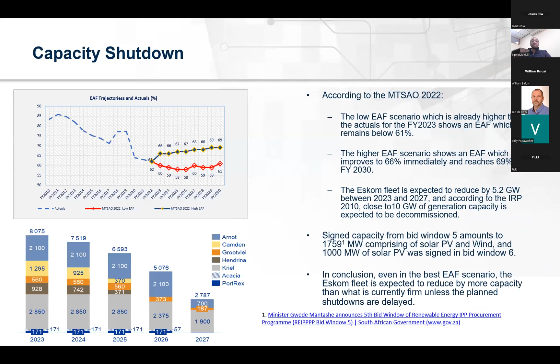The previous slide shows the conventional power generators expected to be shut down according to the MTSAO 2022, and this picture shows the generation capacity expected to come online. Some of it is at an advanced stage, some still in planning. The key thing to notice is that the capacity we're adding is dominated by solar PV and wind, so we're replacing conventional generation capacity with inverter-based generation capacity, which could cause problems for the system operator.